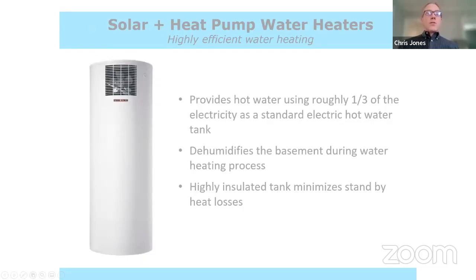So you're in fact using the air, typically within the basement where these tanks are located, using the heat within that air to heat the domestic hot water—for showers, sinks, dishwashers, etc. This is the cheapest way to get your domestic hot water over the course of the year. The numbers bear that out; it's exceptionally cheap to get your hot water this way.